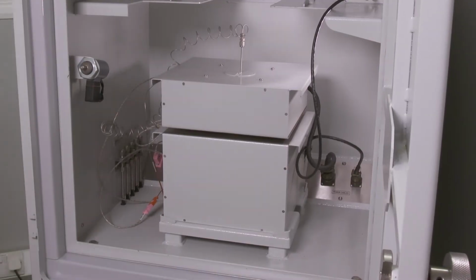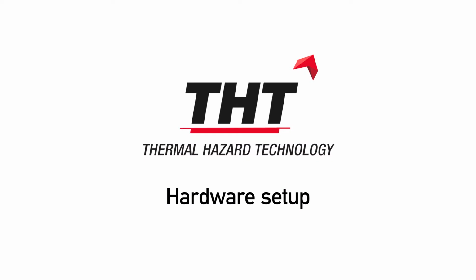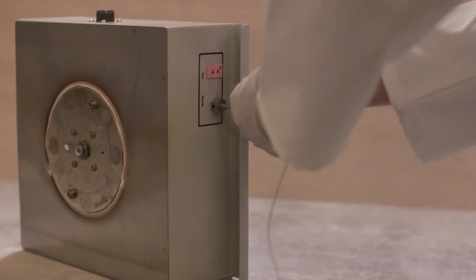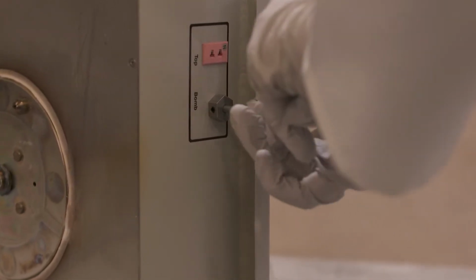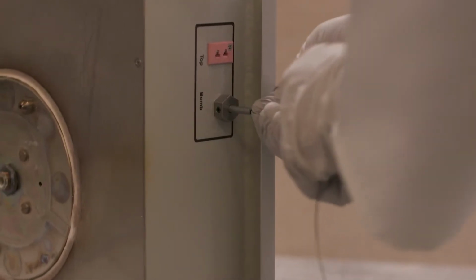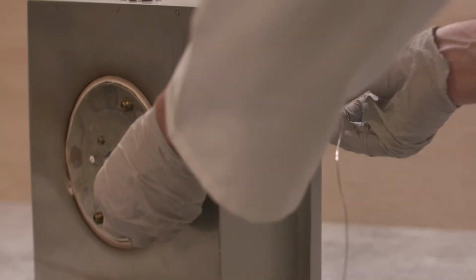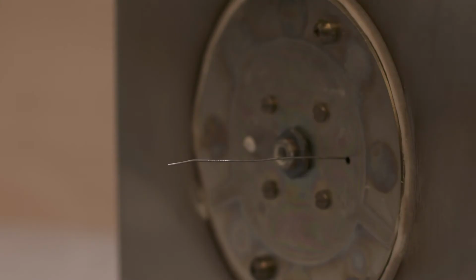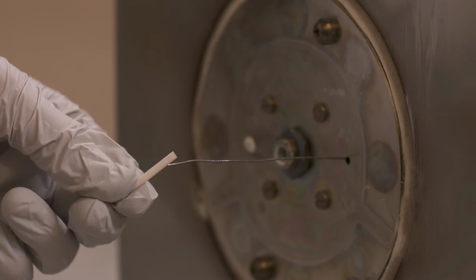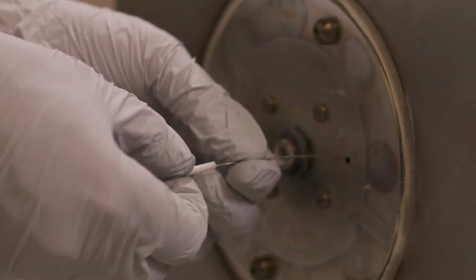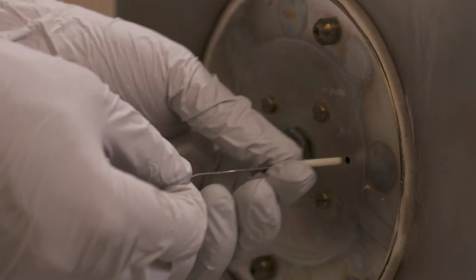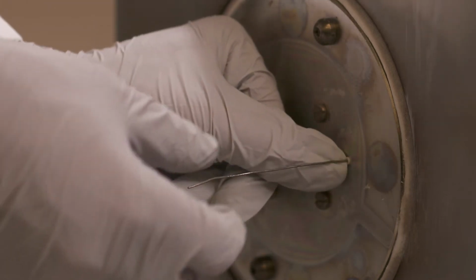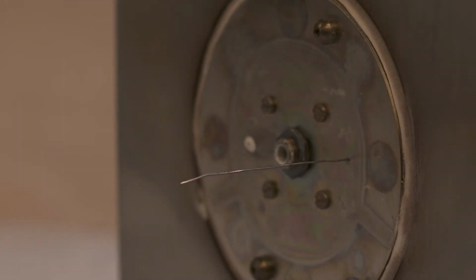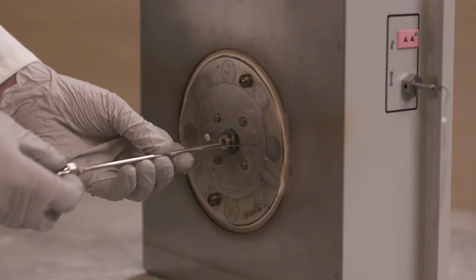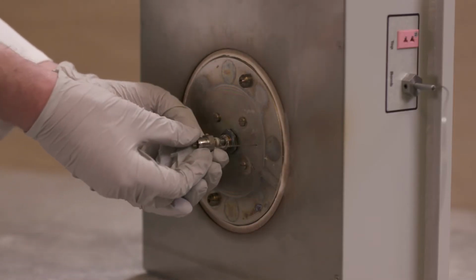The calorimeter should be sitting in the blast box. Hardware setup. Slowly feed the bomb thermocouple through the hole on the side of the calorimeter lid. Take the ceramic tube and feed it over the thermocouple and into the calorimeter lid. Push the through tube through the hole in the center of the calorimeter lid, then tighten with a wrench.